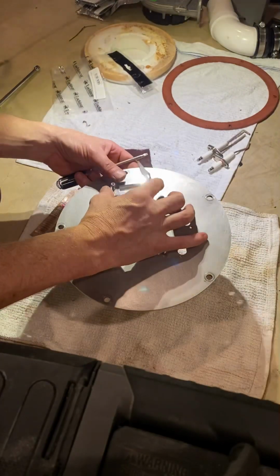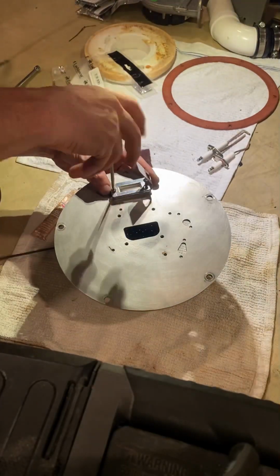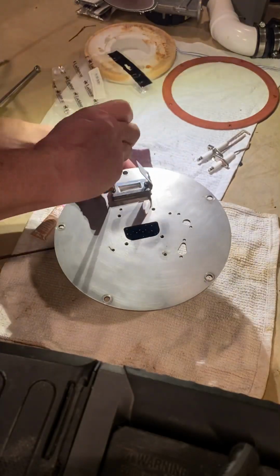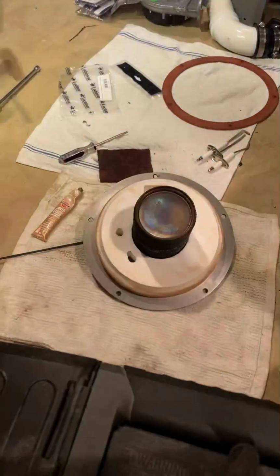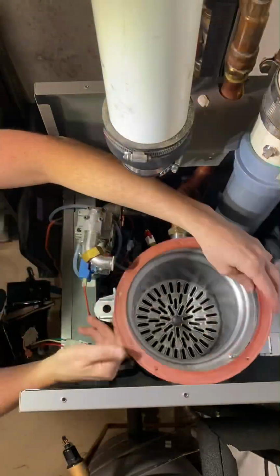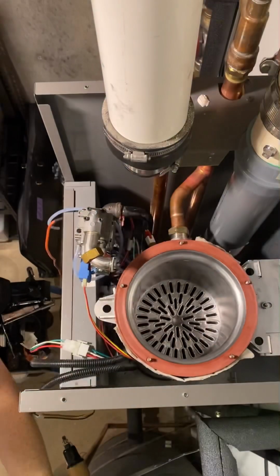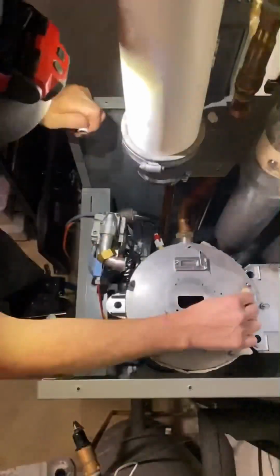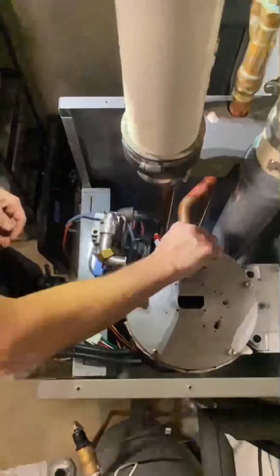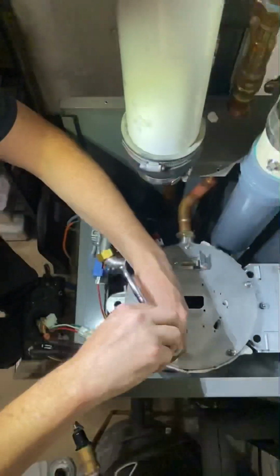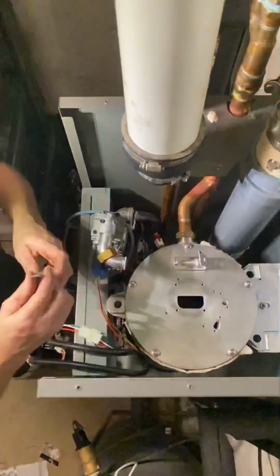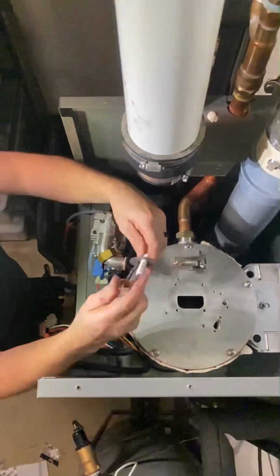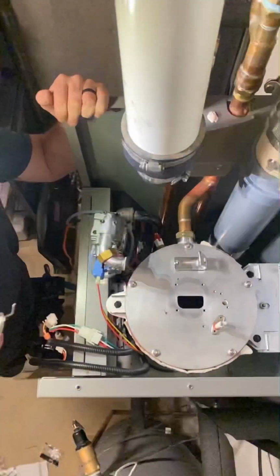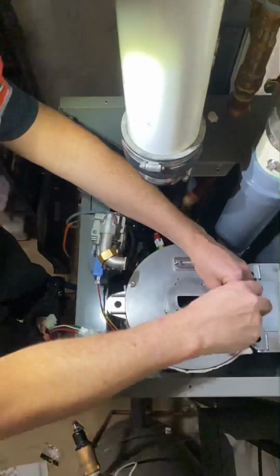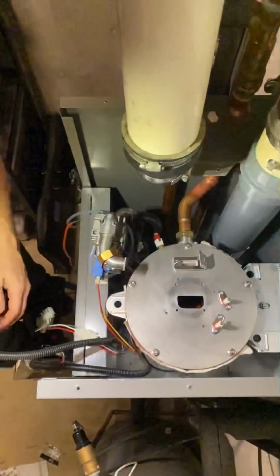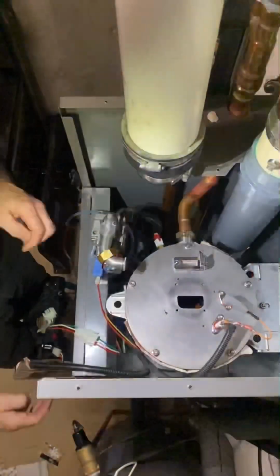I do like to clean the sight glass and replace the gaskets while I'm here. They can start to leak over time, and besides, it's nice to be able to see the warm glow of a freshly cleaned burner. The igniter and flame probe can usually be cleaned using a sandcloth and Scotch-Brite pads. I've heard people say to use a dollar bill to clean them, but that's a literal waste of money. Save your dollar for that extra pump of caramel syrup in your latte. In this case, I replaced both since they are old and I was getting fluctuating readings from the flame probe, flame loss, and eventually the boiler would lock out.